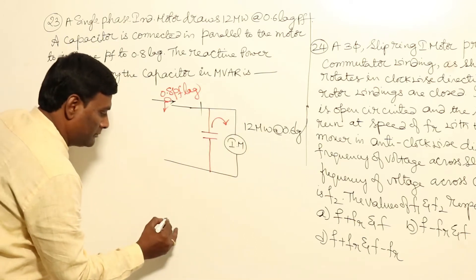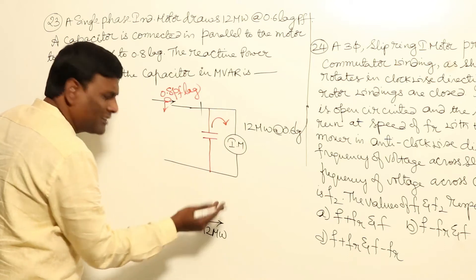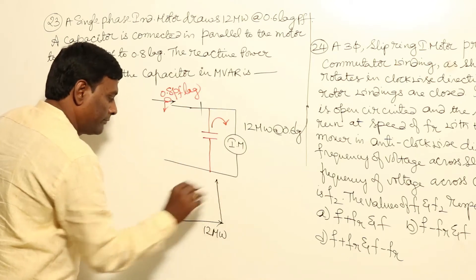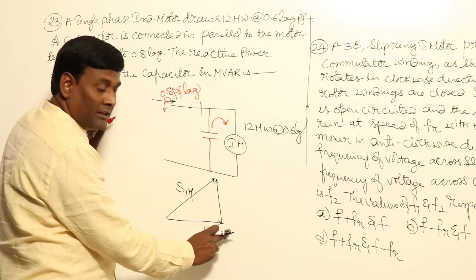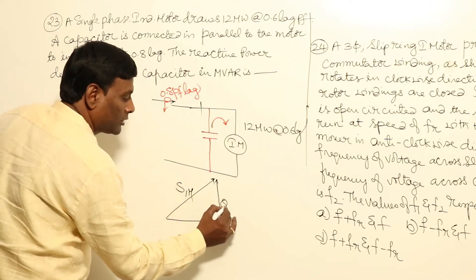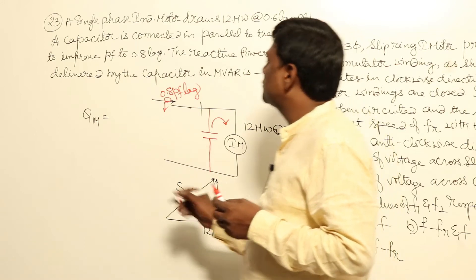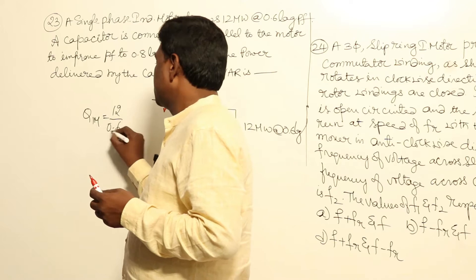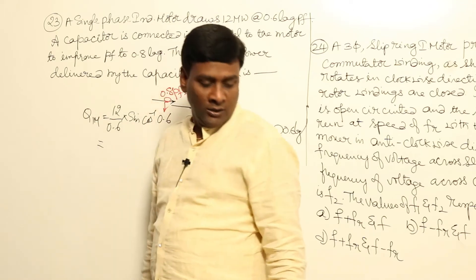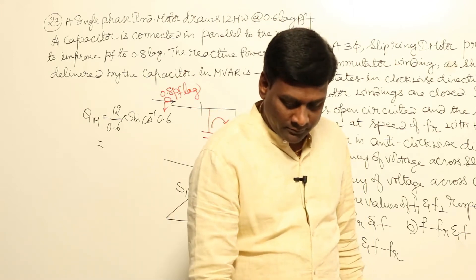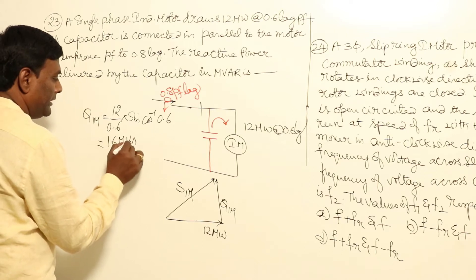For the induction motor absorbing 12 megawatt at 0.6 lag, we calculate the reactive power Q of the induction motor. Active power P is 12 megawatt, so reactive power Q equals 12 megawatt divided by 0.6 MVA, multiplied by sine of cosine-inverse of 0.6. This gives Q of induction motor equal to 16 MVAR.